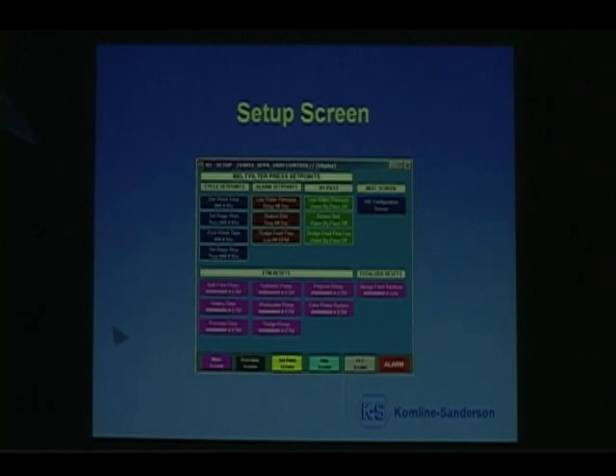This is the setup screen. On the setup screen, you can do many things. The cycle set points for auto, for pre-wash, third stage start, post-wash, cleanup, and third stage stop. And they're settable by just touching them. Another screen will pop up again, allowing you to change the timer. Next to that, you've got your alarm set points for low water pressure, broken belt, and sludge feed flow rate. And they're also settable. By touching them, another screen will pop up, allowing you to change the times.